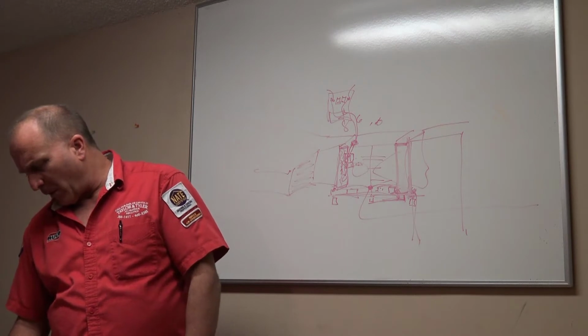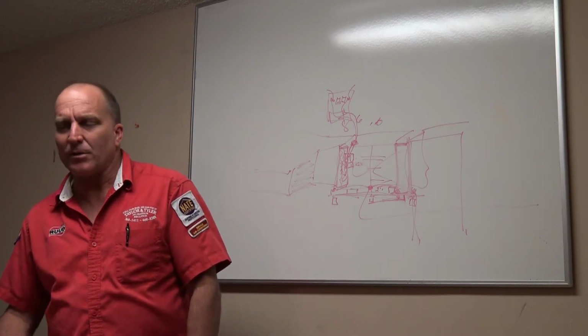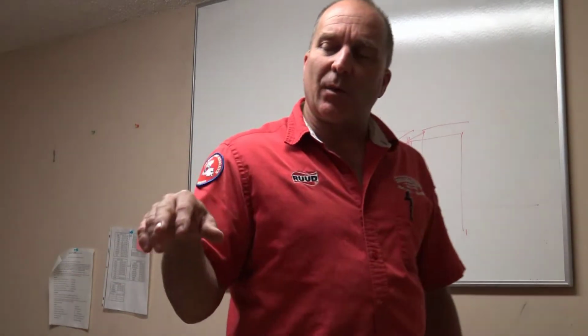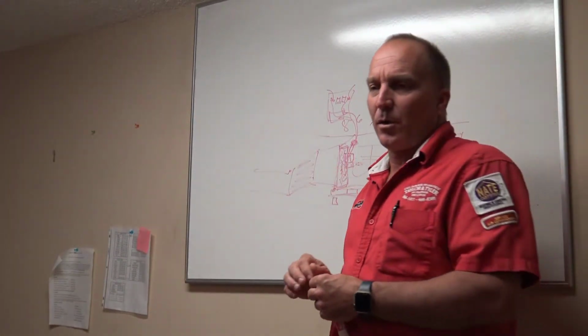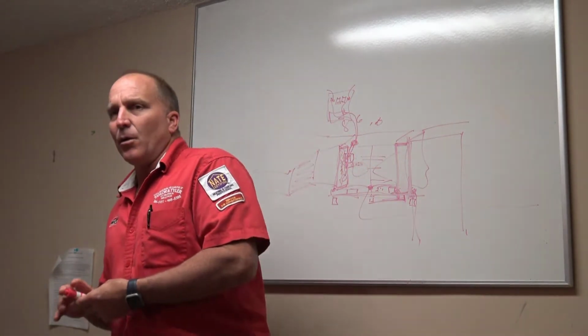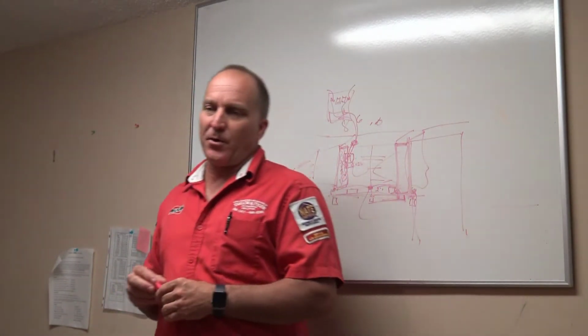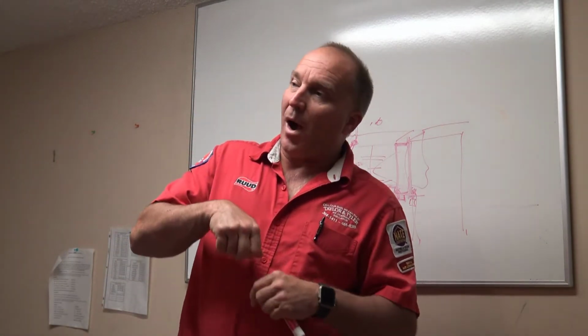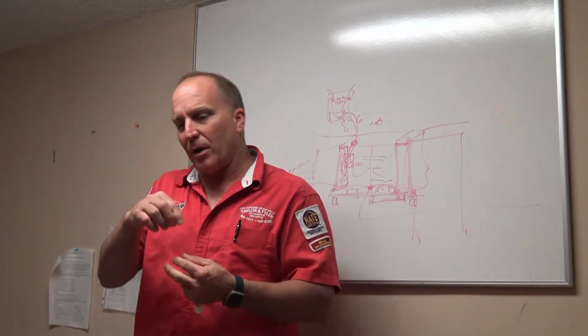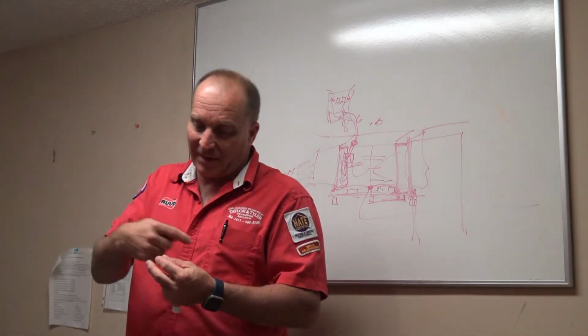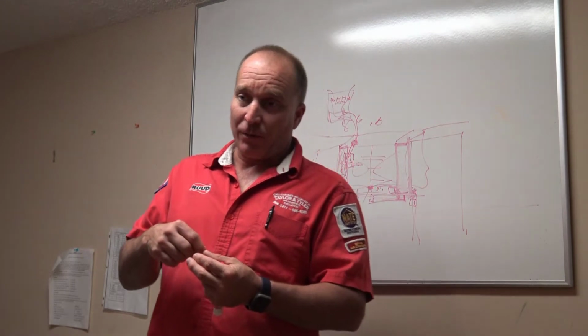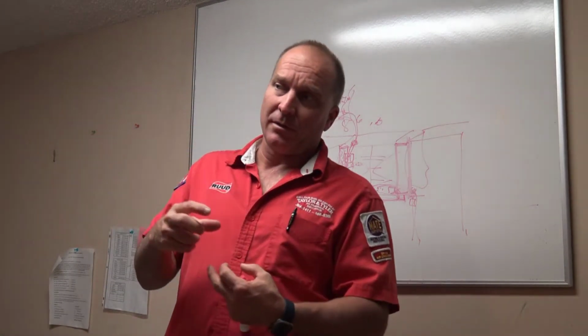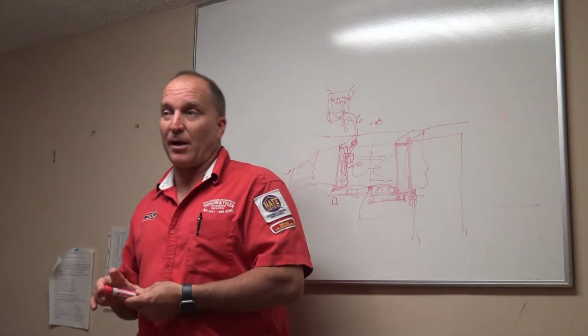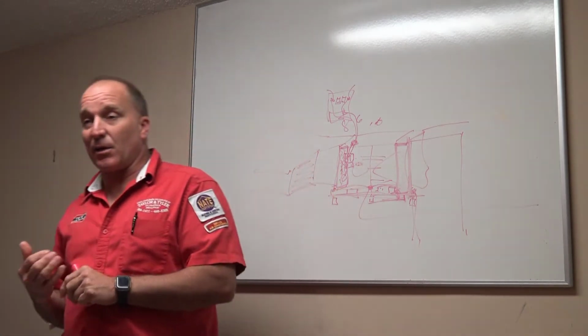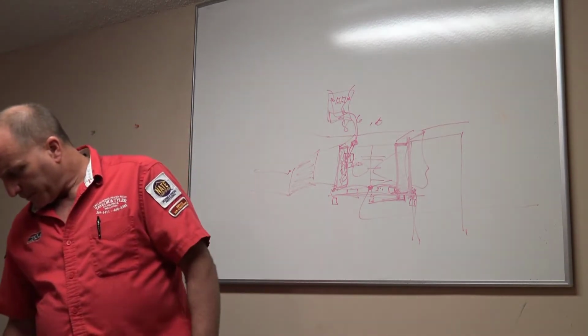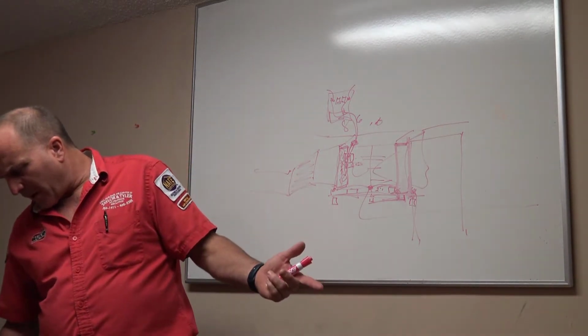Burned wires have burned on the heat sequencer. Replace the heat sequencer. So you've got to remember, on the top of these heat sequencers, on all these plugs, if you don't have good connections onto them, and you're drawing 5 kW heat, which is drawing about 22 amps, then if you don't have a good connection on that wire, it's going to start burning that wire. If it starts burning the wire off the heat sequencer, you're also burning the connection in the heat sequencer. So if that wire is pretty much burning off the heat sequencer, you may want to replace the heat sequencer as well, because if not, you'll probably be back replacing it. So replace the heat sequencer with the wire when it's burning like that. Open means that the heat sequencer does not close when energized.